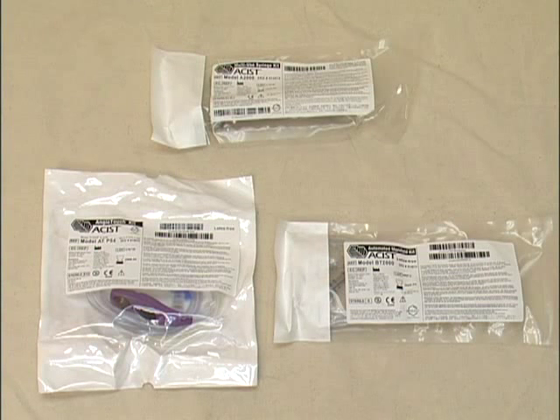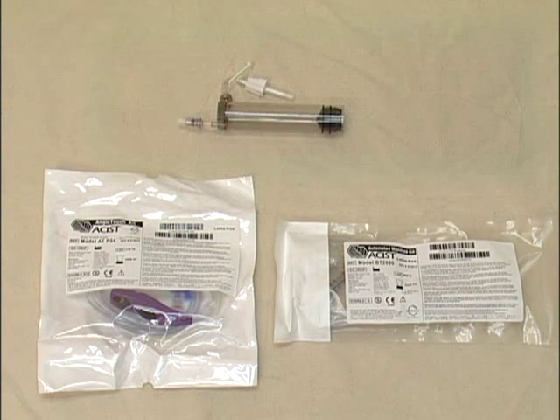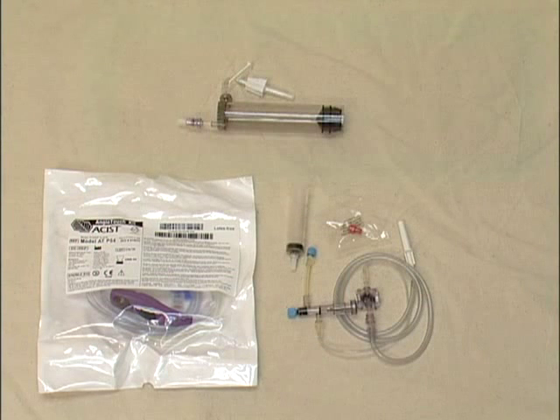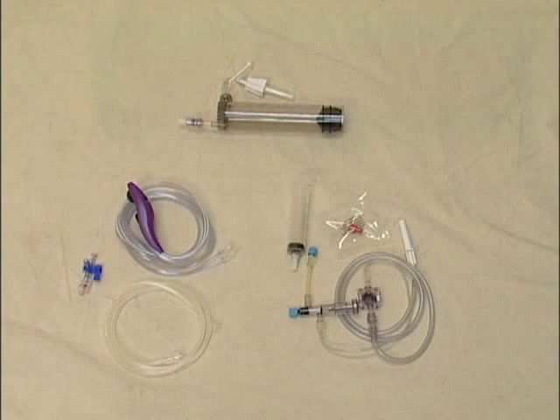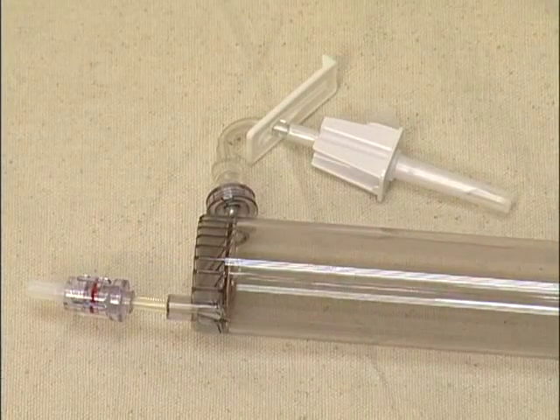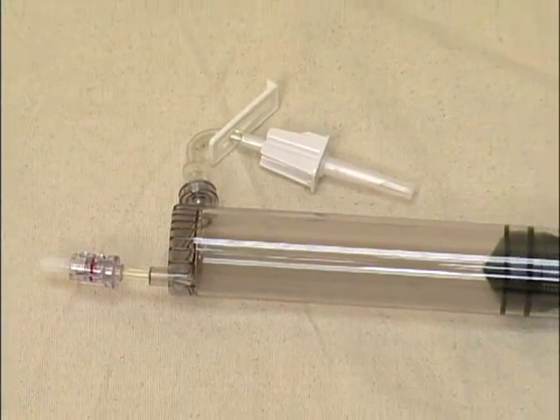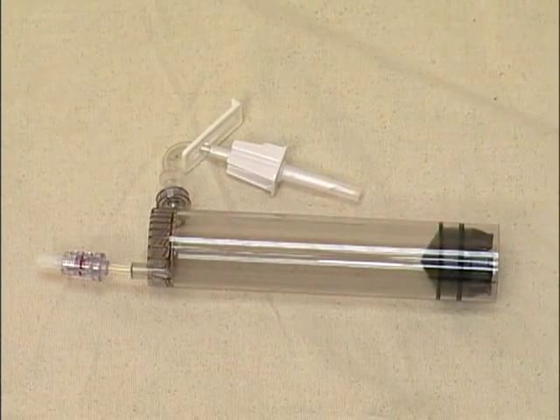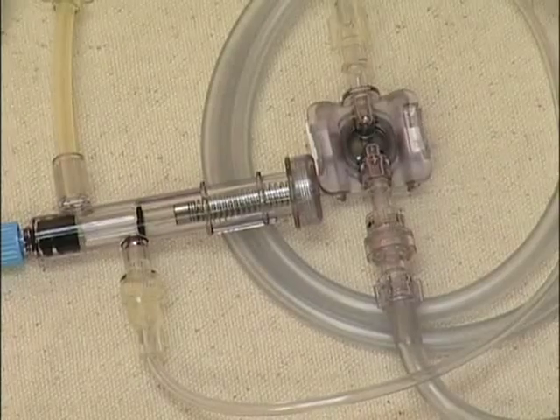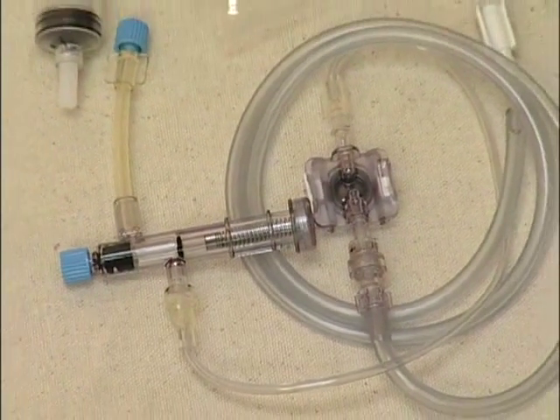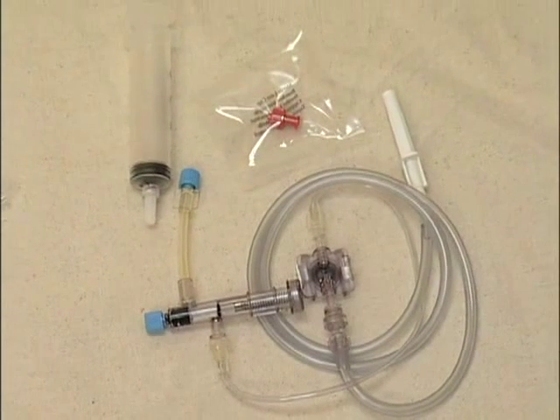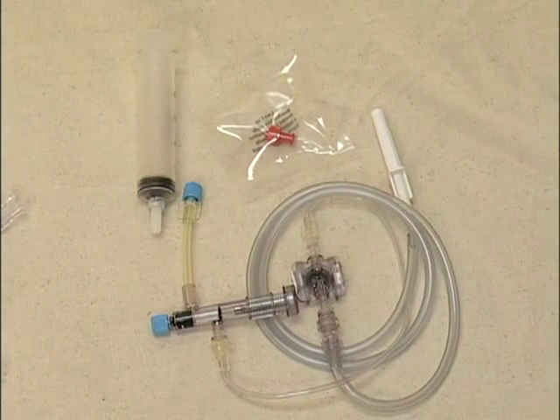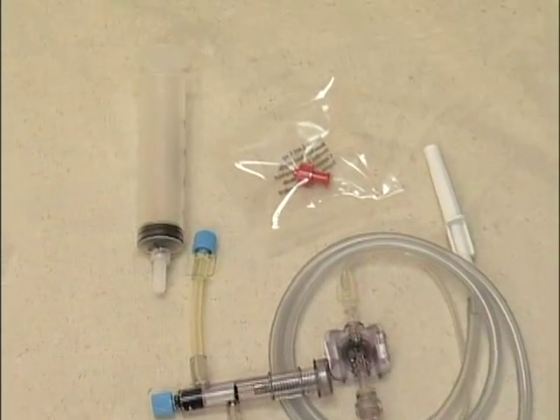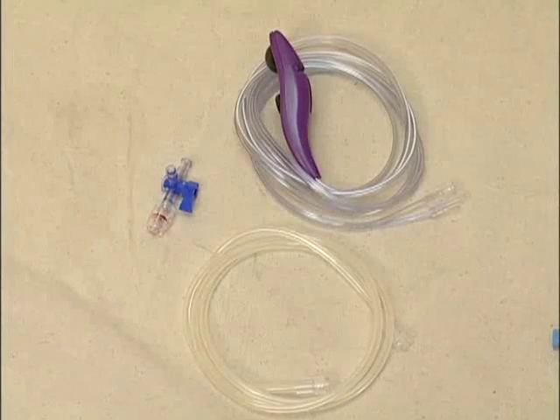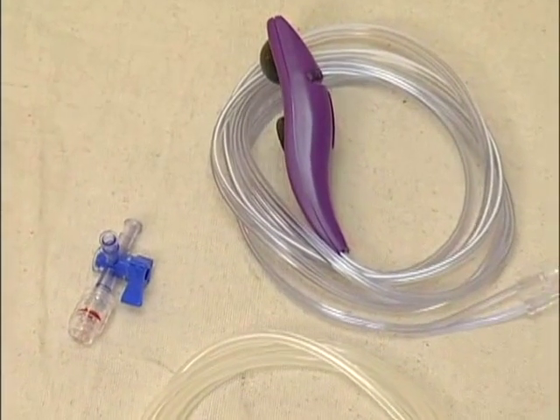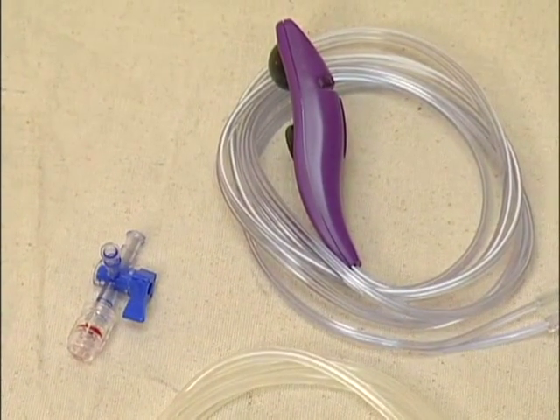The ACIST disposable kits consist of three separate packs: the A2000 syringe kit, the BT2000 manifold kit, and the ATP54 hand controller kit. The A2000 syringe kit is a 5-use kit. It consists of the syringe barrel and the spike assembly. The BT2000 manifold kit is a single-use kit, and it consists of the saline line, the manifold, the pressure transducer, a hand syringe, and a sterile cap. The ATP54 kit consists of the hand controller, the high-pressure tubing, and the three-way stopcock.